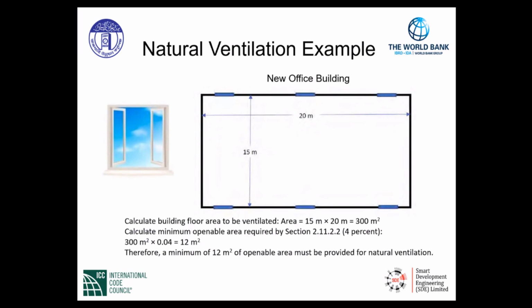We need to calculate the building floor area to be ventilated. That's our first step. So a simple calculation of the area of the building is 15 meter by 20 meter, which gives us 300 square meters. We need to calculate the minimum openable area required by the section, indicating 4% of the area to be openable to the outdoors. So we come in and we calculate the minimum openable area. We take 300 square meters times the decimal equivalent of 4%, which is 0.04, and that equates to 12 square meters of minimum openable area that must be provided for natural ventilation.